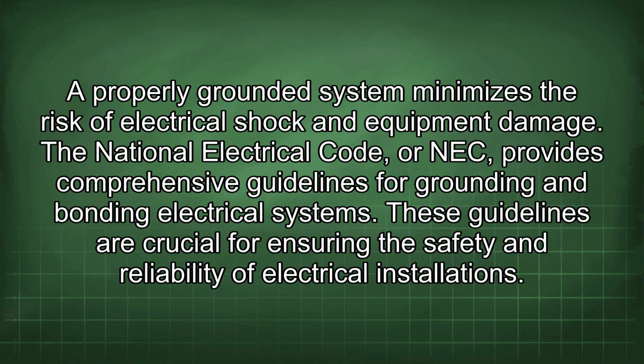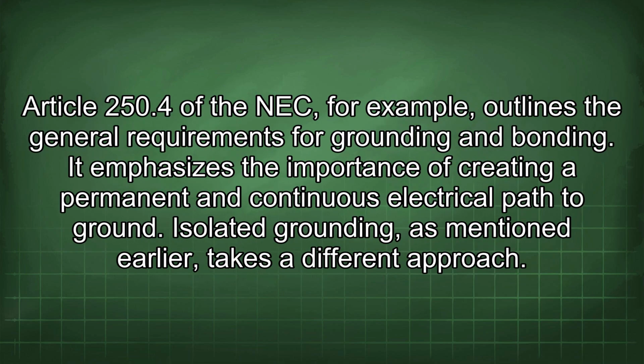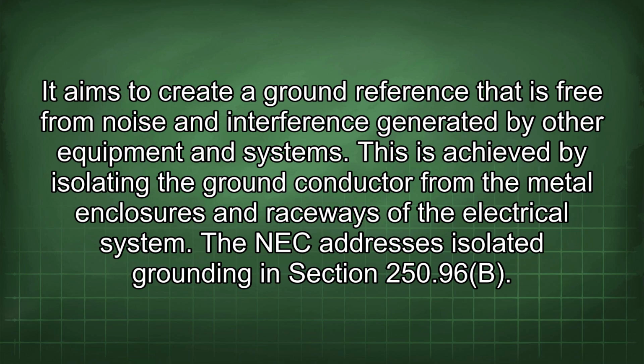A properly grounded system minimizes the risk of electrical shock and equipment damage. The National Electrical Code, or NEC, provides comprehensive guidelines for grounding and bonding electrical systems. These guidelines are crucial for ensuring the safety and reliability of electrical installations. Article 250.4 of the NEC, for example, outlines the general requirements for grounding and bonding. It emphasizes the importance of creating a permanent and continuous electrical path to ground. Isolated grounding, as mentioned earlier, takes a different approach. It aims to create a ground reference that is free from noise and interference generated by other equipment and systems. This is achieved by isolating the ground conductor from the metal enclosures and raceways of the electrical system.